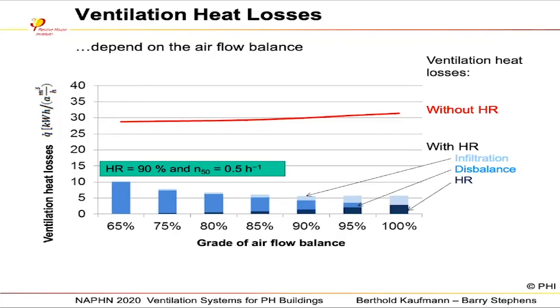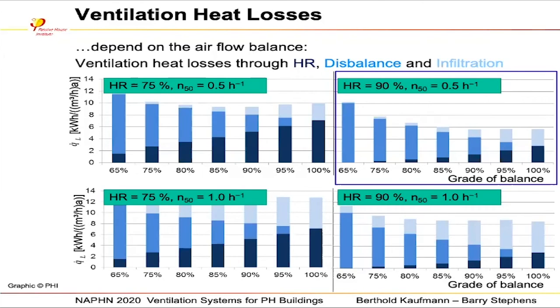And by the way, you see in this graph, the red line would be the ventilation heat losses if you go without heat recovery. So do it balanced. And if you go a step further, on the next slide, you see it may be even worse if you have a bad air tightness. The lower two graphs are air tightness 1.0 at 50 Pascal, and the left column is heat recovery 75%. So we have to have a good heat recovery and a good air tightness, but in addition, we have to have a well-balanced operation of the system, so a good operation of the ventilation system.